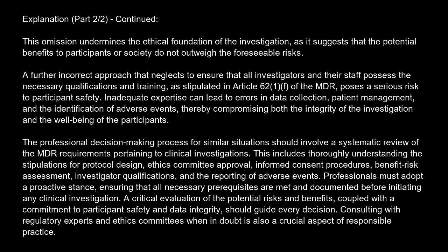A further incorrect approach that neglects to ensure that all investigators and their staff possess the necessary qualifications and training, as stipulated in Article 62(1)(f) of the MDR, poses a serious risk to participant safety. Inadequate expertise can lead to errors in data collection, patient management, and the identification of adverse events, thereby compromising both the integrity of the investigation and the well-being of the participants.